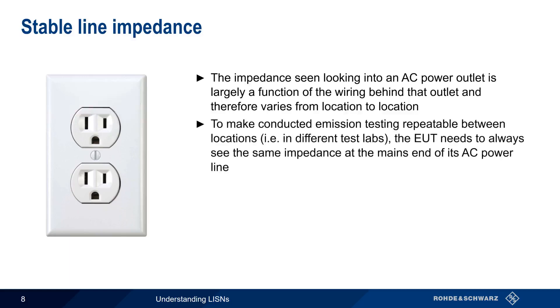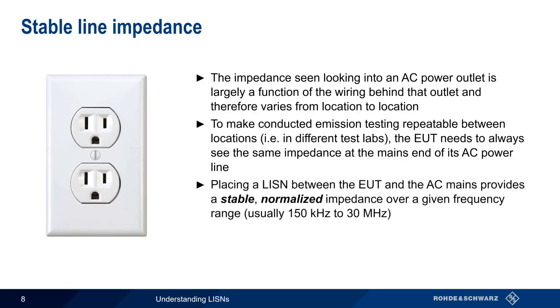A LISN stands for Line Impedance Stabilization Network, so it's helpful to explain what we mean by stable line impedance. The impedance seen looking into a standard AC or mains power outlet is largely a function of the wiring behind that outlet, and therefore this impedance will vary from location to location and from outlet to outlet. This isn't a problem for everyday use, but in order to make conducted emissions testing repeatable between locations — that is, between different labs — the EUT should always see the same impedance at the mains end of its AC power line. Using a LISN between the EUT and the AC mains outlet provides a stable, normalized impedance over a given frequency range, usually 150 kHz to 30 MHz.